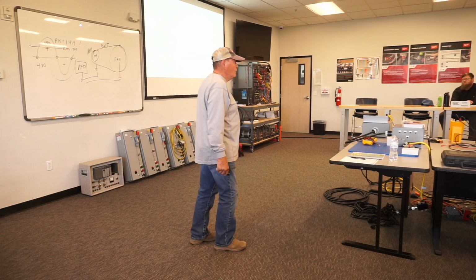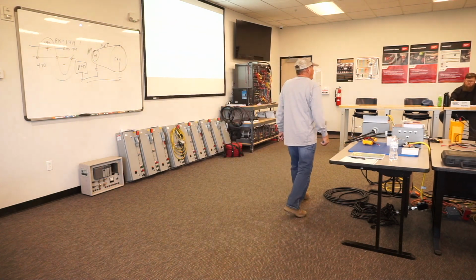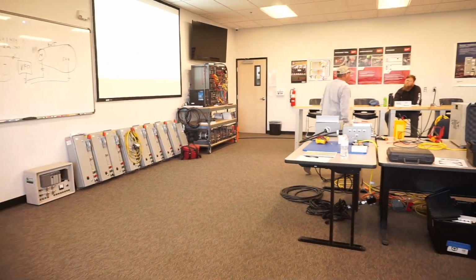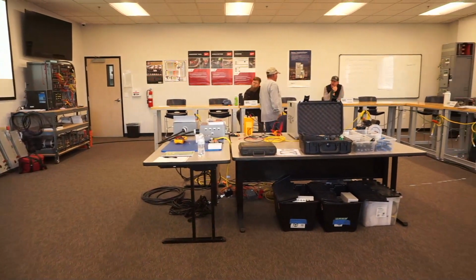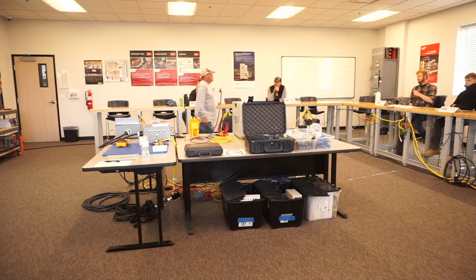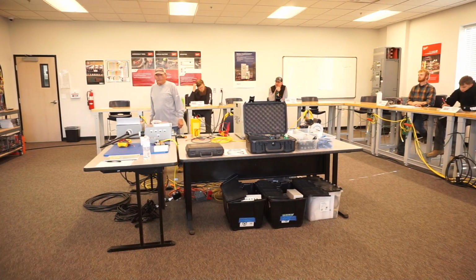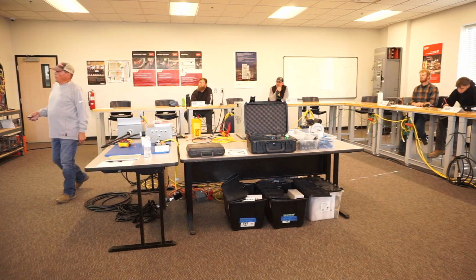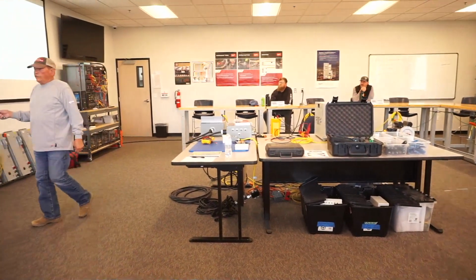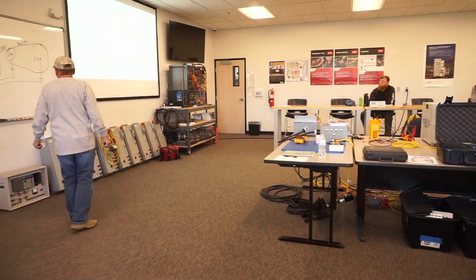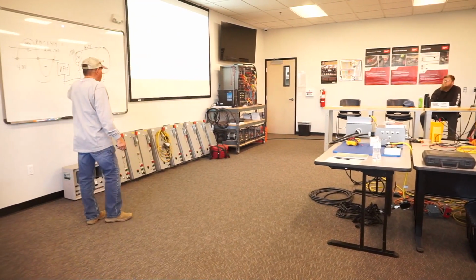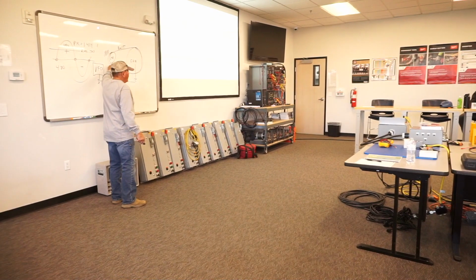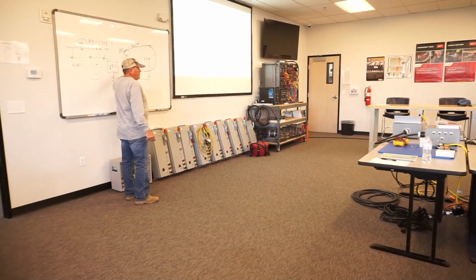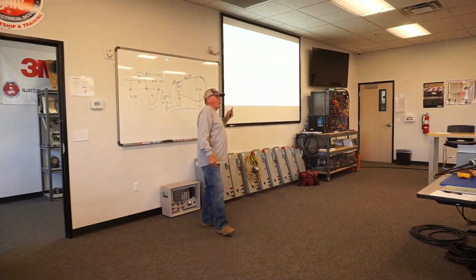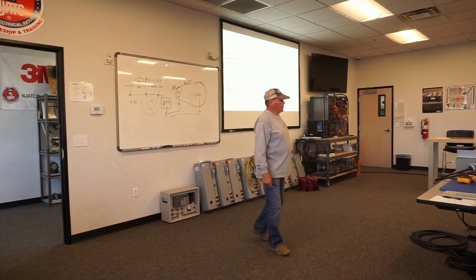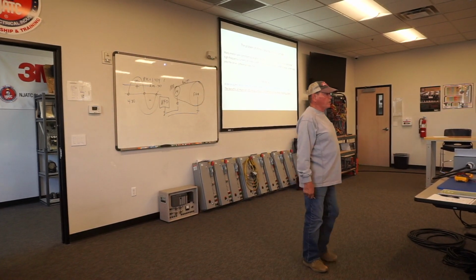Do you fix that by bonding the motors and putting filters in? Yes, absolutely. In fact, my first encounter with this was out at Summit Racing. I told the contractor out there, here's your problem, and the fix is to bond this motor. The temperature on the motor dropped 40 degrees after you bonded the motor. That's all you do, is bond the motor.